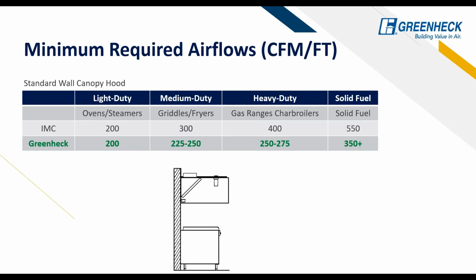Okay, so speaking of the IMC, the International Mechanical Code that I mentioned earlier, that references airflow rates. Sometimes you'll see us size a hood and send you something at 250 CFM per linear foot for a gas range charbroiler, and you might think, wow, we're way under what we need to be. That's just because we're listed. An ETL listed hood is allowed to run at these recommended airflows from Greenheck. We don't have to go to the IMC ratings. The IMCs are for unlisted hoods. If some mechanical contractor wanted to build his own hood that wasn't listed, that's what you need to run those at. So just a reference there.